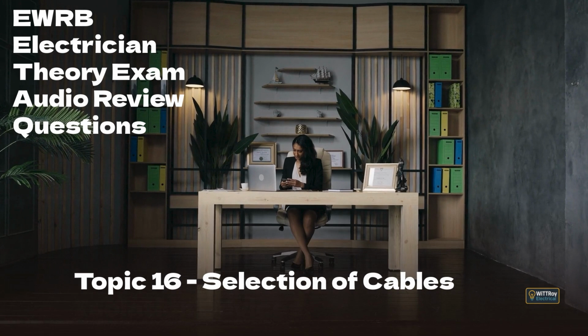Insulation has a temperature limit. The cable current rating is set so the conductor stays below that limit under the installation conditions, protecting insulation life and safety. Review question 23. If ambient temperature rises, what happens to allowable cable current carrying capacity?